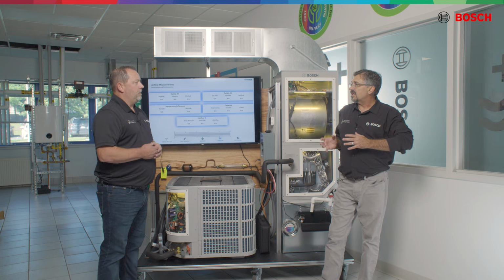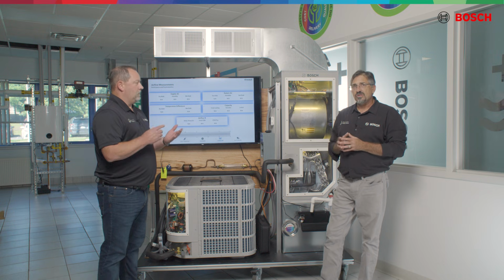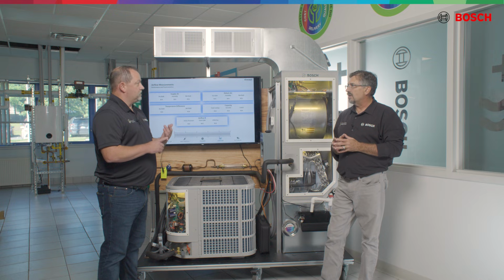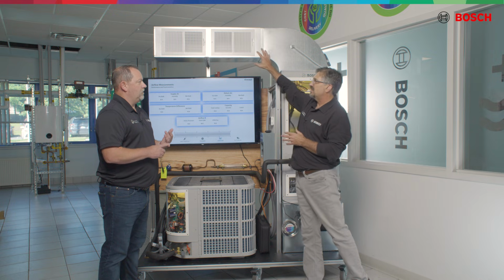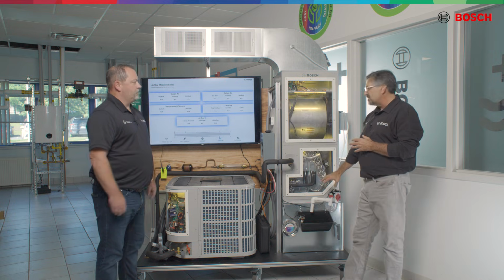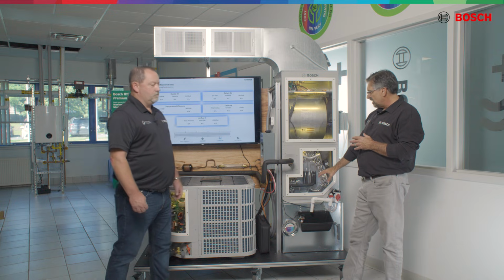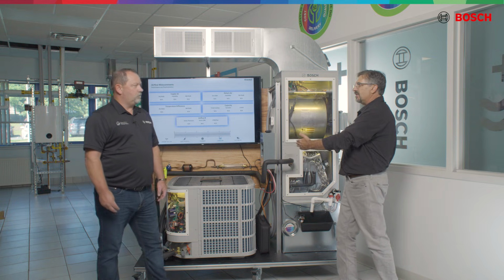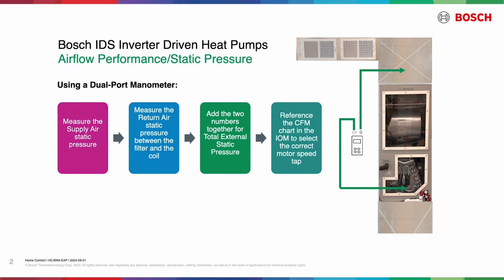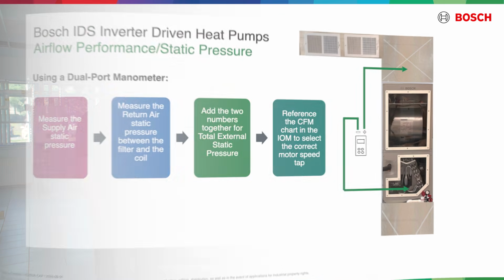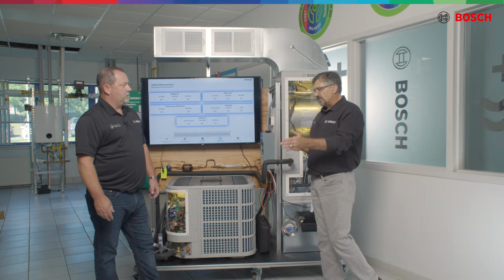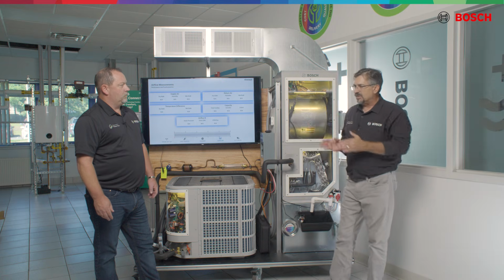We need really basic information, Chris. Every technician should have a static pressure manometer. What we're looking to do is get our supply static pressure and our return static pressure. When we're checking return static, we want to be behind our filter. We need the pressure drop through our filter, so I can't be on the other side of the filter. Otherwise, I'm not including it. That's right. So when we come behind the filter, we're getting our total static pressure.